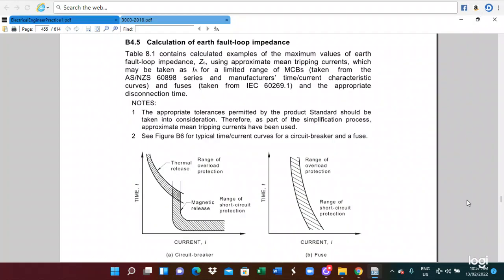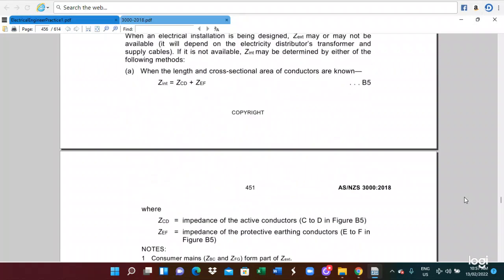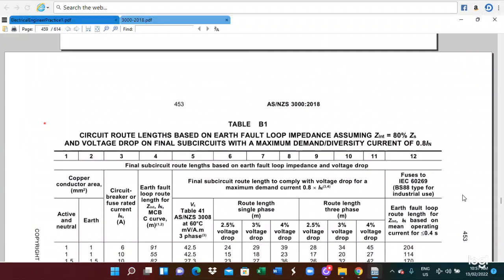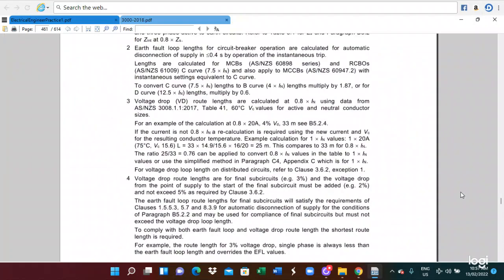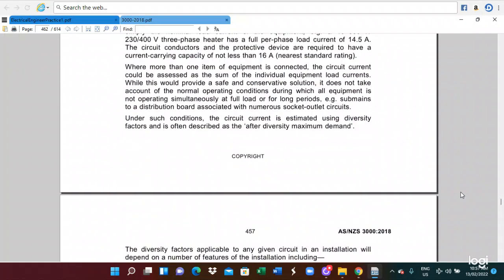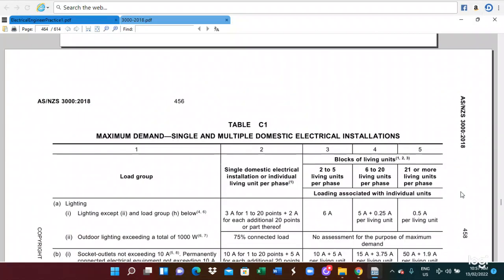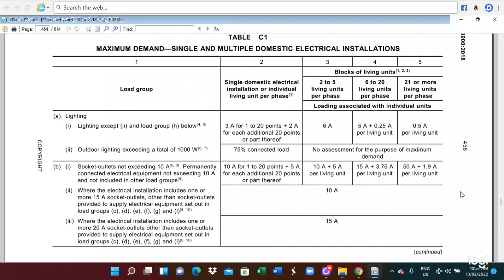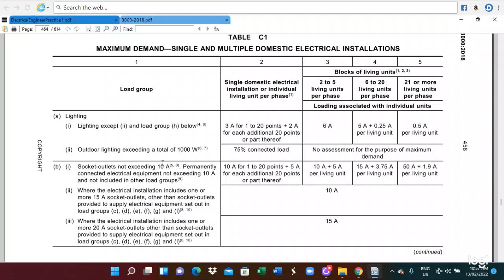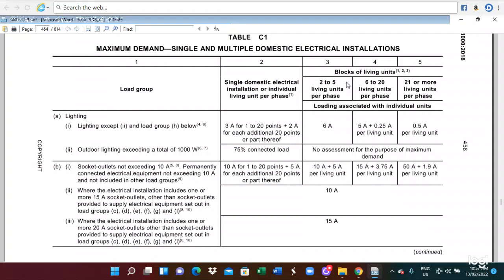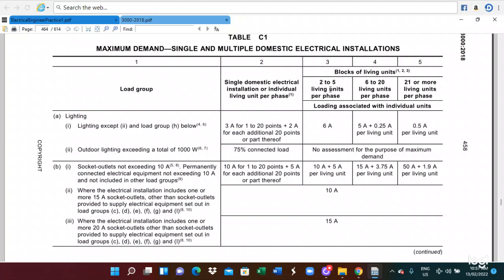So this is the appendix table. Tables C1, C2, C3 are utilized to calculate the maximum demand of the consumer main. Table C1 means a lighting load group. For a single domestic installation, we have to utilize 3 amperes for the first 1 to 20, and 2 amperes for each additional 20. And this is for the block living unit: 2 to 5 living units, 6 to 20 living units, and 21 or more living units. This is the lighting we calculated.